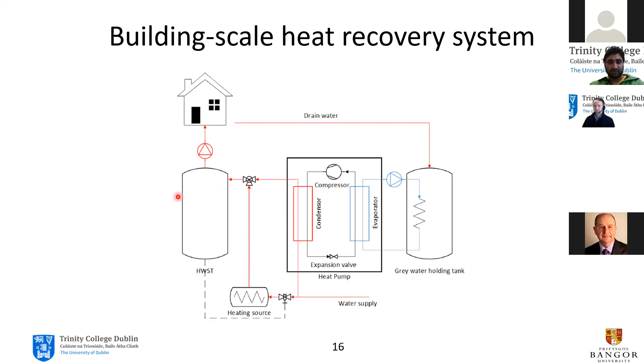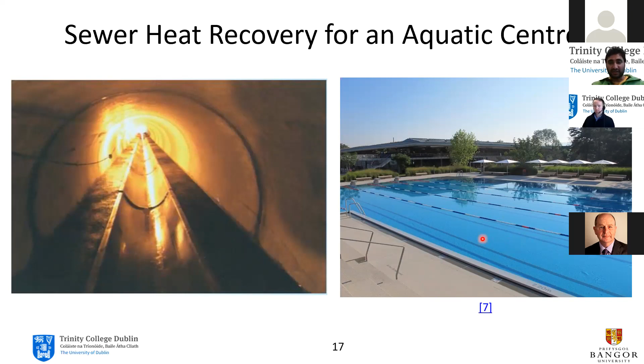This is a practical example of a drainage system made up of a metallic plate in Zurich, Switzerland. The cross section of this metallic plate is semicircular, and the cold water pipelines are underneath this metallic plate and embedded in it. And the hot water, you can see here, surrounds it, so that the fresh cold water coming into the supply lines will recover the heat from the hot wastewater present in the drainage system. So preheating can be achieved, and we can use the preheated water in leisure centers like swimming pools and various other locations to reduce our electricity bills.